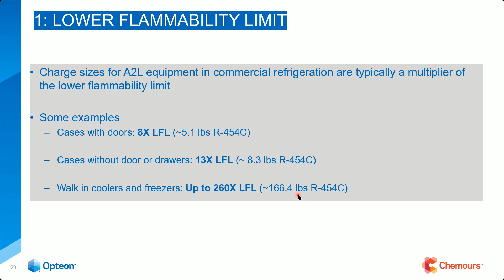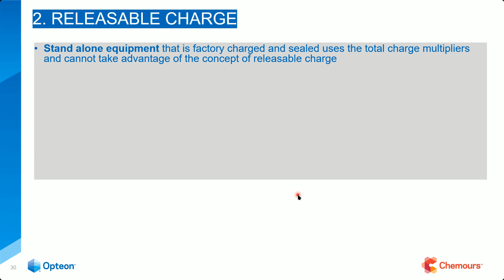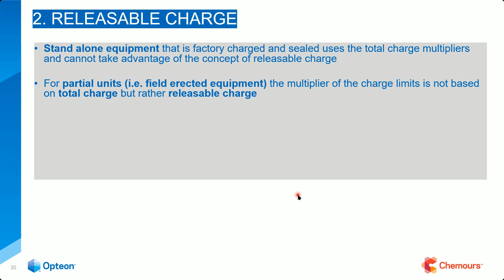The second part: releasable charge. Standalone equipment that is factory charged and sealed uses the total charge multipliers. It cannot take advantage of the concept of a releasable charge. So if it's standalone and charged from the factory, it cannot take advantage of the releasable charge. For partial units, i.e. field-erected equipment, the multiplier of the charge limit is not based on total charge, but rather on releasable charge. And I'll explain what that means in a little bit.